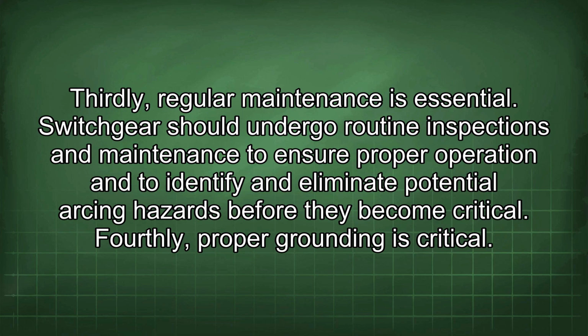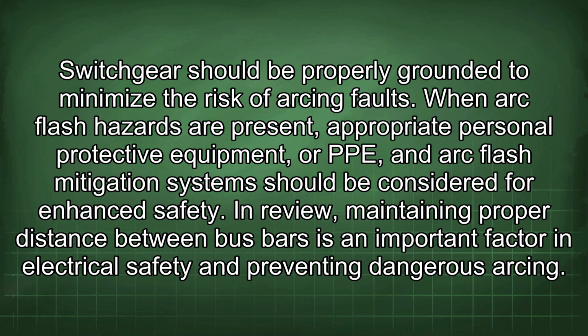Switchgear should undergo routine inspections and maintenance to ensure proper operation and to identify and eliminate potential arcing hazards before they become critical. Fourthly, proper grounding is critical. Switchgear should be properly grounded to minimize the risk of arcing faults. When arc flash hazards are present, appropriate personal protective equipment, or PPE, and arc flash mitigation systems should be considered for enhanced safety.